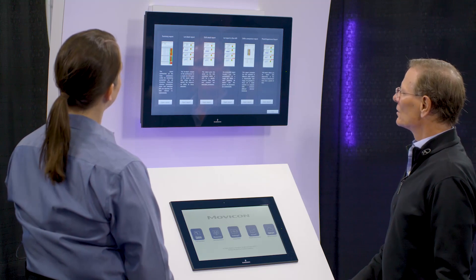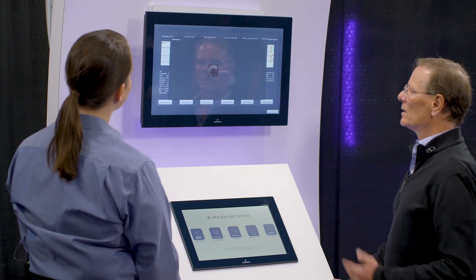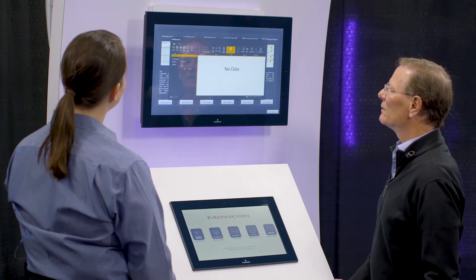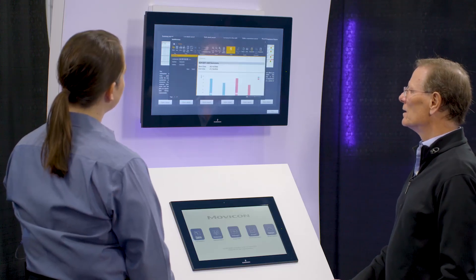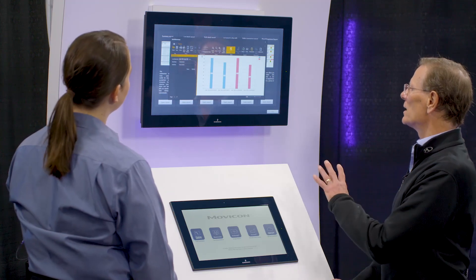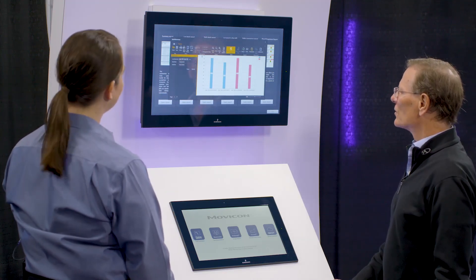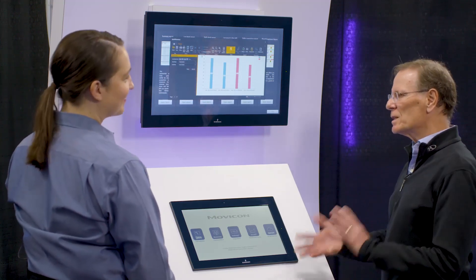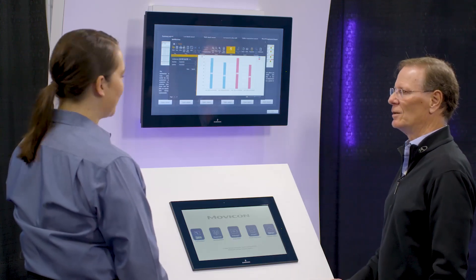Sometimes people like to compare one machine to another. A handy report is the shift comparison report — I select it, choose which assets to compare, select all, and hit submit. Look at this report: I've got line one and line two with a couple of different metrics. Line one is doing better than line two — 90% versus closer to 80%. You'd want to investigate that and improve your overall efficiency. That's reporting built in, out of the box, and easy to use.